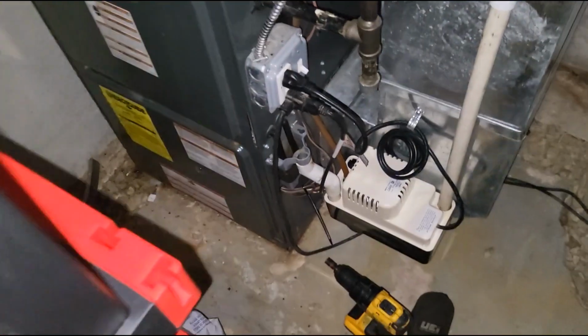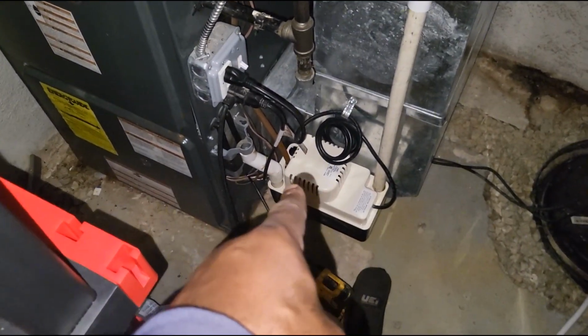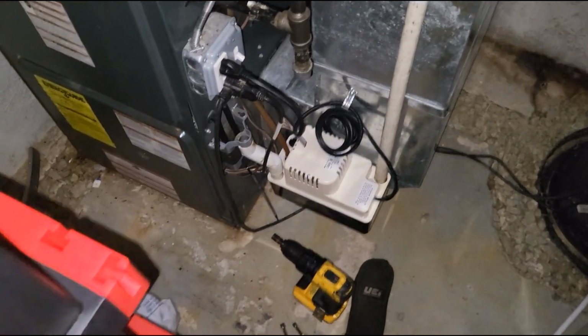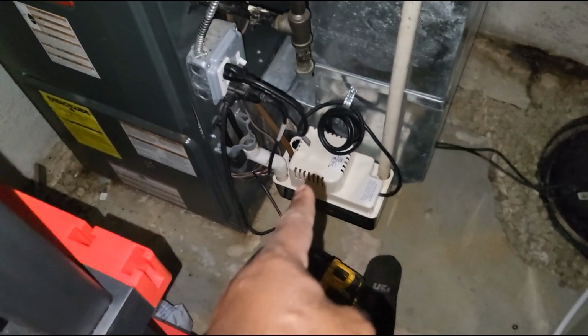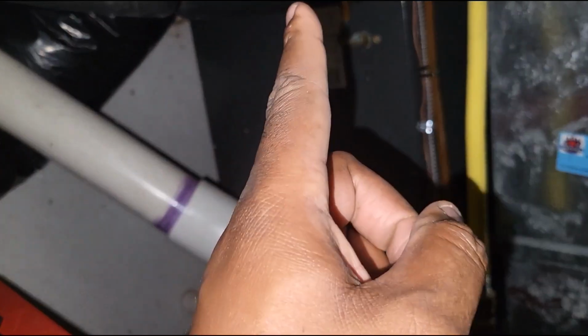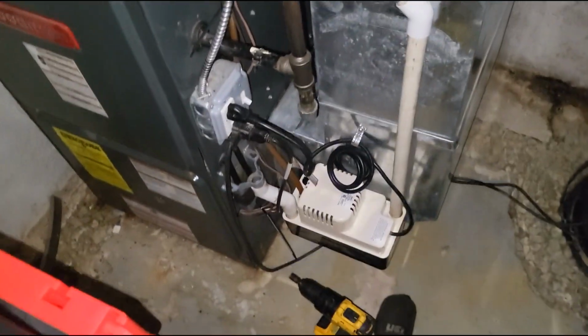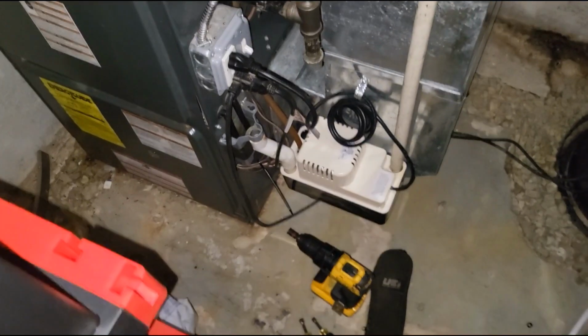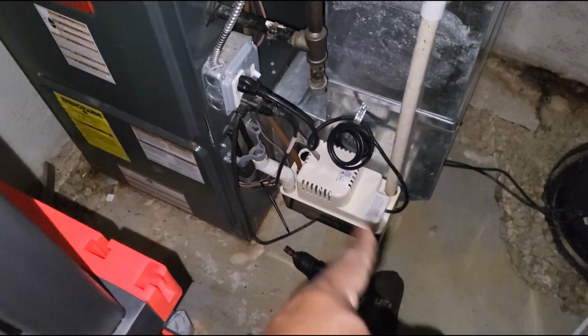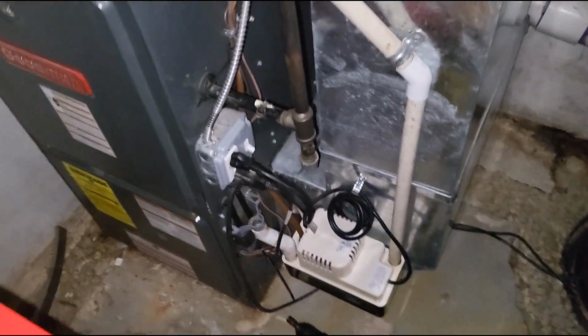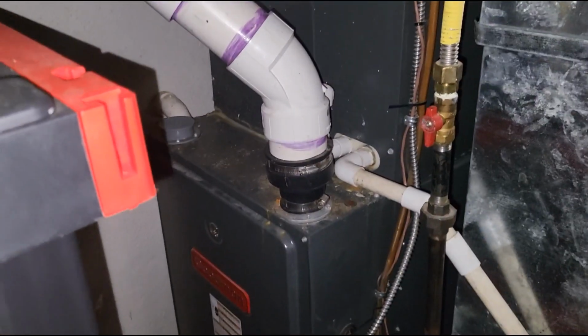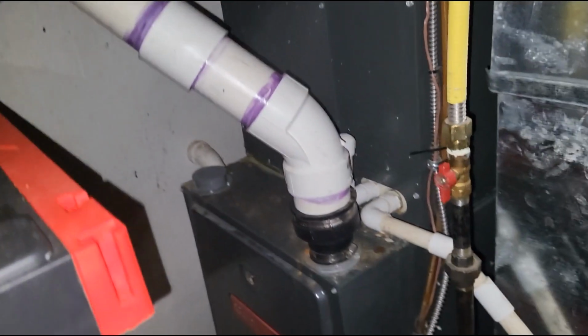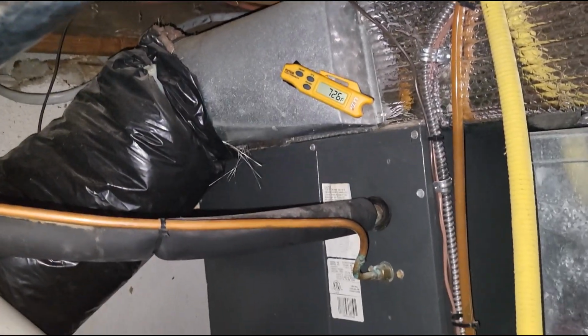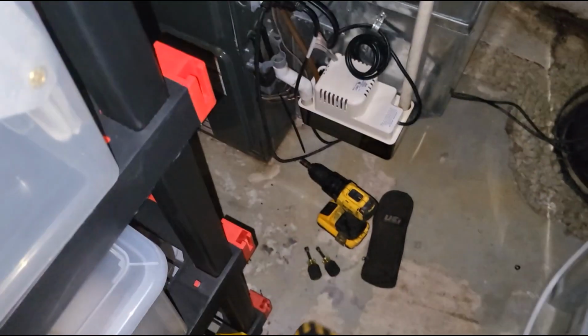As far as history here, I think I either made a short or a video about this last summer, I believe. They had two issues. Two years ago, I think we replaced an AC capacitor outside. And then last year, the customer said that they came down here and the whole floor was soaking wet, and the water went away once they turned the AC off, and we had to replace the condensate pump. So besides the pump inside and the capacitor outside getting replaced, nothing else has been done to this unit. I just turned the unit off because I had to go back and get some tools to open up this unit. But yeah, guys, with that being said, let's get started.